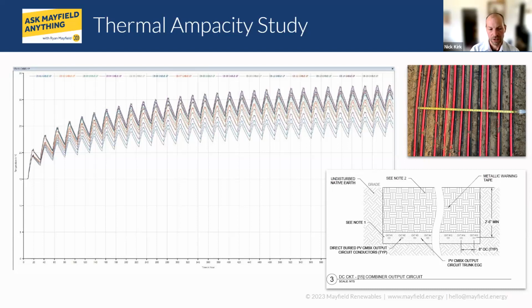Further analysis was required, though. One of the sites had wetlands that they were installing on and around, and part of that requirement was to minimize disturbance. And so they came to us and asked to reduce the circuit spacing down to 3-inch on center, which you can see in that upper right picture. And the resulting analysis gave us a max conductor temperature of 40 degrees or 47 degrees C. And so our goal there is to stay under the insulation temperature rating for the conductor.